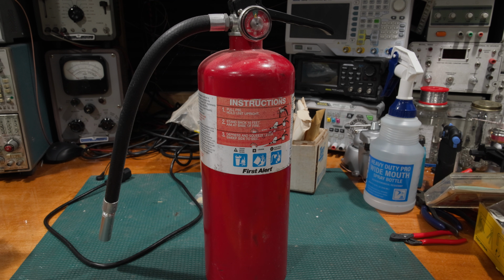The breaker's there to save the wire. It's not there to save a person. So breakers are not life-saving devices. But in terms of a fire risk, the biggest risk is actually arcing connections. So if you have a connection that's sizzling, if you have a socket that's loose, if you have a socket that's sizzling, these are some of the bigger risks of fire, as opposed to just leaving a device on 24/7. Arcing gets incredibly hot, borderlining on a plasma, and it can very easily start a fire. So tight connections, new outlets, nothing loose, things like that.